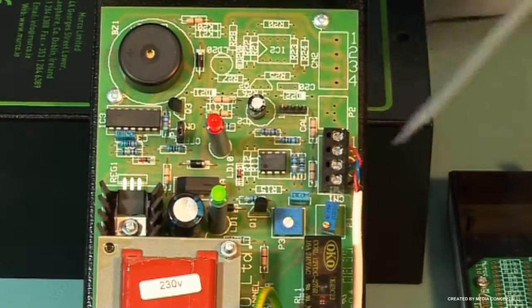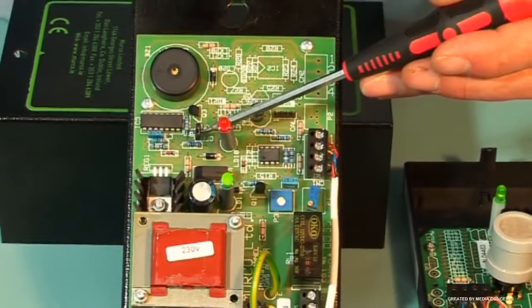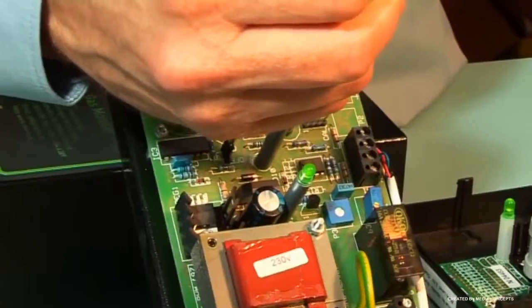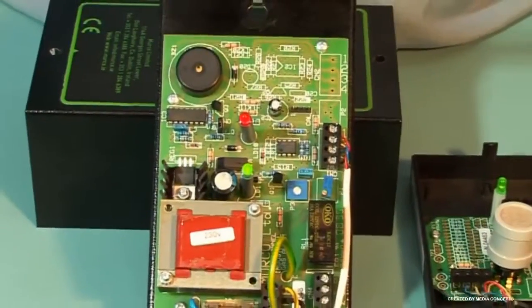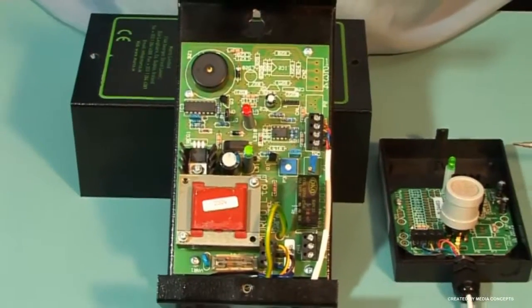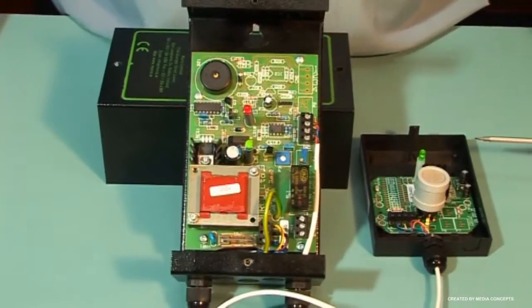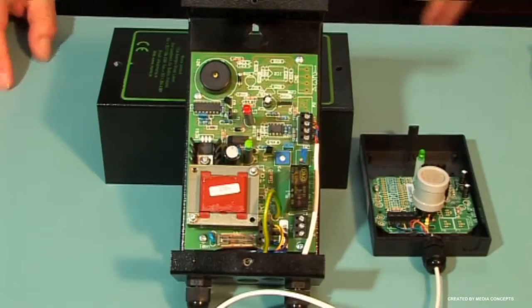The delay on the unit is set by jumper JP1 and should be moved to the off position to remove delay. The jumpers are normally red or black in colour. Removing the jumper silences the sounder and disables the alarm relay.